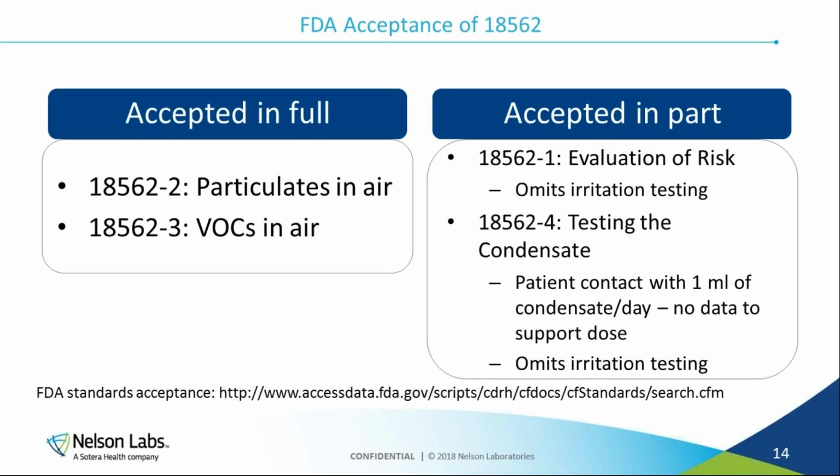And then in part 4, again, it goes on to talk about testing this leachate, and it does not talk about testing for irritation. So we would want to make sure we're incorporating all the testing outlined in 10993 part 1, and that 18562 is supplemental testing. And then I've listed here where you can find that information published by the FDA.